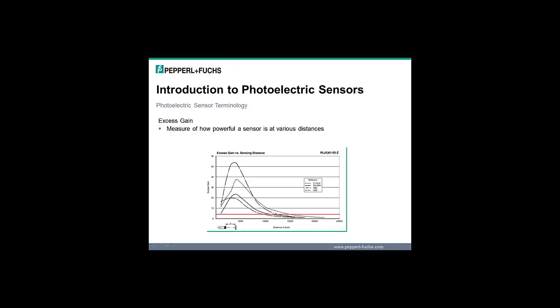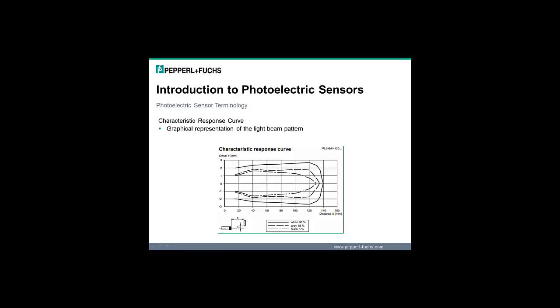Excess gain is a means of measuring how powerful a photoelectric sensor is at various distances. Excess gain does not have units of measurement; rather it is a ratio defined as the amount of light at the receiver versus the amount of light required to change the output state. A characteristic response curve provides users with a graphical representation of the light beam pattern. Due to the nature of light, the beam is symmetrical in three-dimensional space, although it is shown in just two dimensions. These graphs are simple guidelines and should not be used as precise values, but they can be used as a means of estimating the sensor's light beam diameter and lateral switching points.